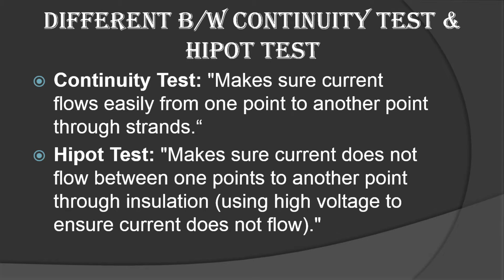Now, the difference between the continuity test and the HiPot test: The continuity test makes sure that current flows easily from one point to another point through the strands. The HiPot test is the opposite — it makes sure current does not flow between one point to another point through the insulation of the cable. This is the main difference between the continuity test and the insulation test.